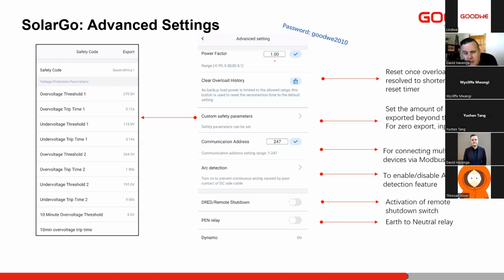So with this, it's a bit more fine tuning. You have to assess the site's power factor with a meter, and then adjust the power factor up and down until you improve the site's power factor. The majority of installers do not touch this, but on bigger commercial sites, it's always good to check the power factor of the site, because a perfect 1 power factor on the output of a device can negatively impact the power factor of a site.